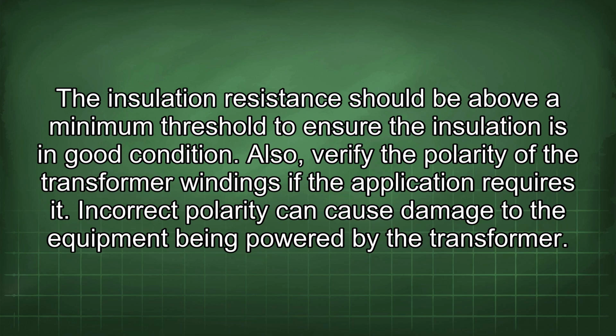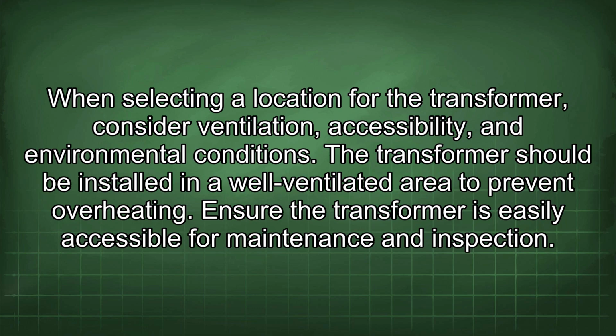Also, verify the polarity of the transformer windings if the application requires it. Incorrect polarity can cause damage to the equipment being powered by the transformer. When selecting a location for the transformer, consider ventilation, accessibility, and environmental conditions. The transformer should be installed in a well-ventilated area to prevent overheating.